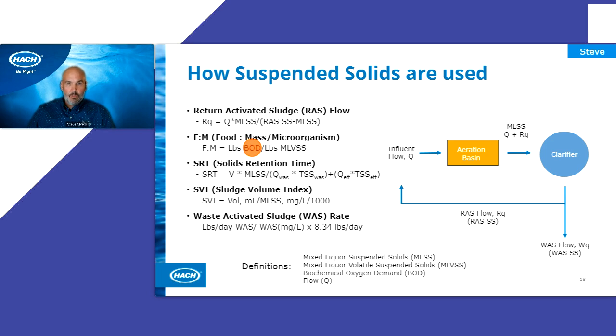The food to microorganism ratio is a pretty important parameter, where we're monitoring how much biomass is in the system relative to the amount of food, in this case BOD, coming in. That has important implications on how fast biological treatment reactions, or kinetic rates as we refer to them, are taking place, so this is where optimization lives. SRT is one I'll talk about in more detail in the next slide, but it essentially takes into account the mixed liquor suspended solids, so TSS, if you will, as a correlation there. In the aeration tank, how much biomass is in there relative to how much you're getting rid of on a regular basis.